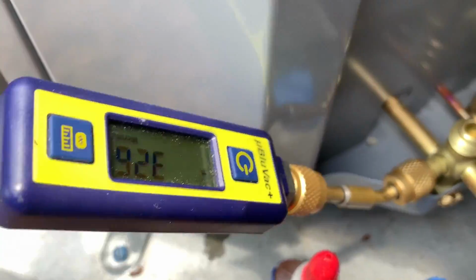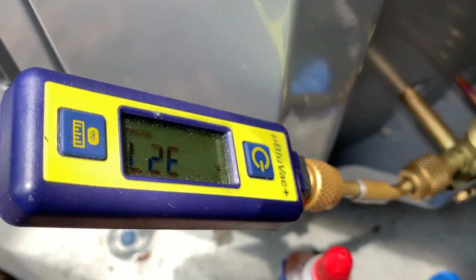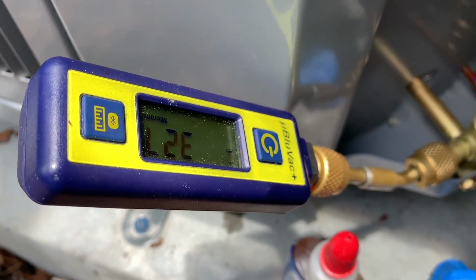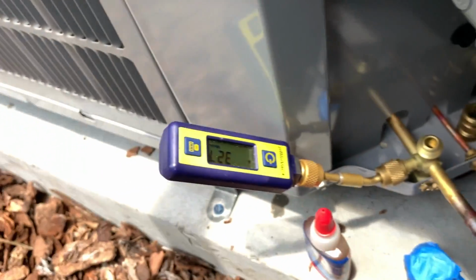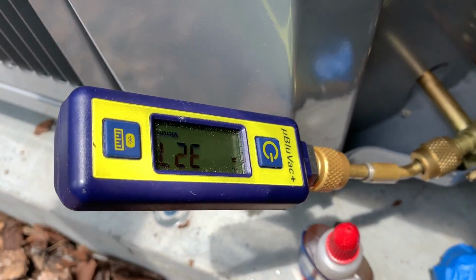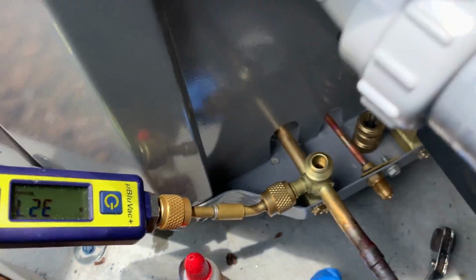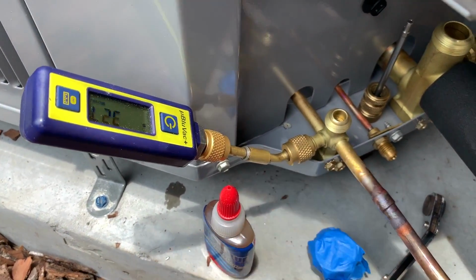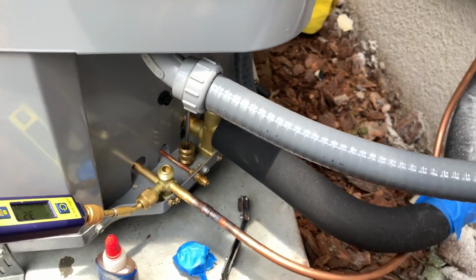This little guy's been holding steady now for 10 minutes or so. I think it's moved 5 microns, something like that. I mean, this is a tight system. Again, every system has microscopic leaks that will show up under this level of deep vacuum, even just the seals that you have on your connections, but that's a very tight system. So we're ready to release the charge.